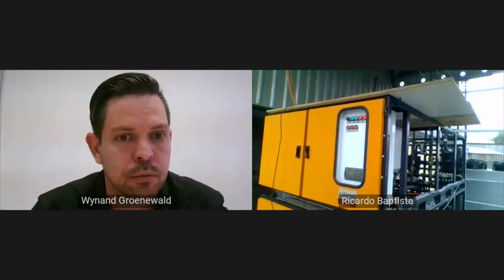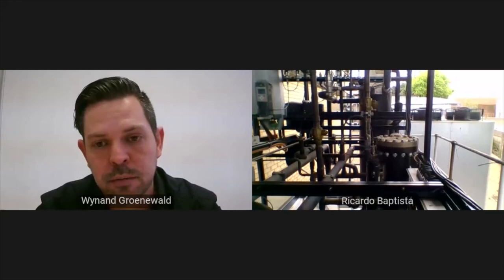Each rack is equipped with an electronic control board containing controllers for the high pressure valves and system operation. All lead compressors are fitted with variable speed drives for efficiency and capacity control. Looking at the oil separators, you can see the parallel compressors, and on the far left the VFDs can be displayed. All equipment is fitted with high pressure special components designed and manufactured for CO2 purposes.